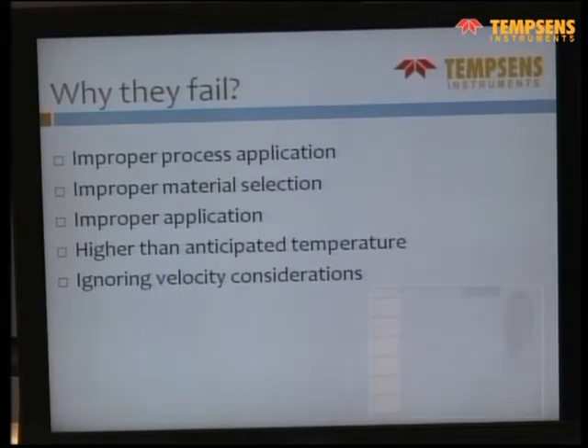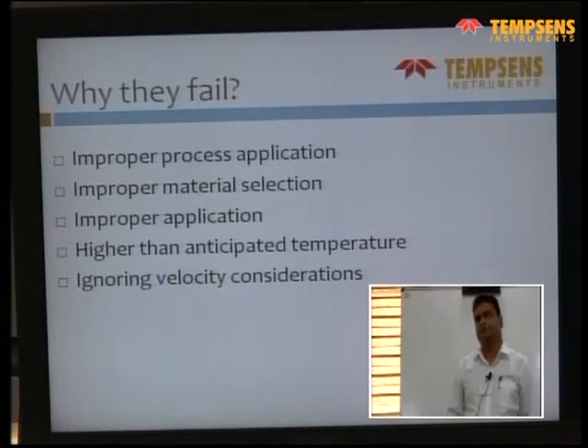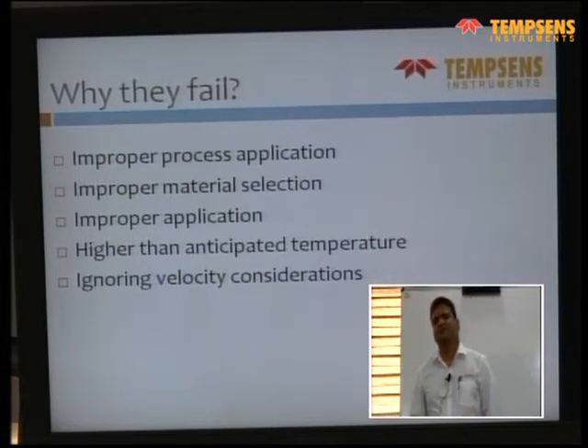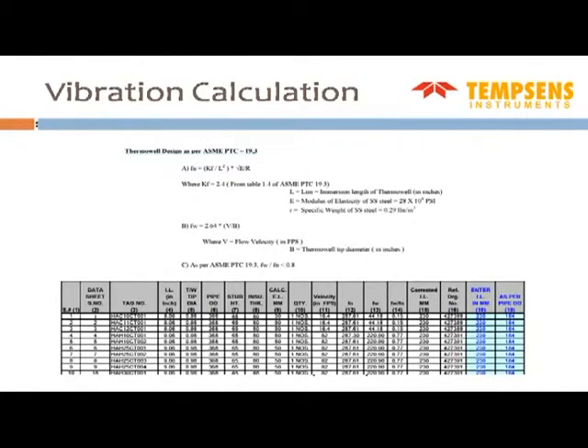Coming to why thermowells fail: improper process application, improper material selection, higher than anticipated temperature, and ignoring velocity considerations. Velocity calculations are made specifically for power plants, where you know the fluid and the flow. There is a standard called PTC 19.3, where if you give in all the process parameters and the type of thermowell, it tells you the natural frequency of that kind of system, and you have to see that this natural frequency is not crossed. This kind of calculation is done for all thermowells for power plants.